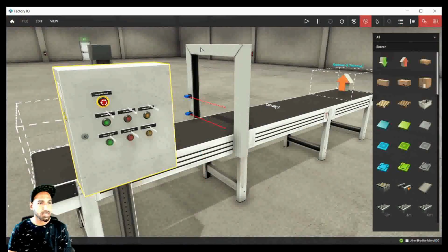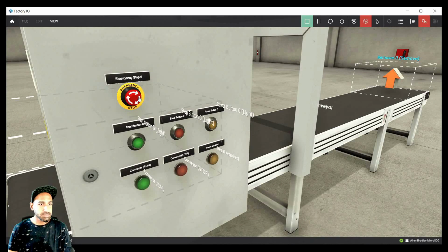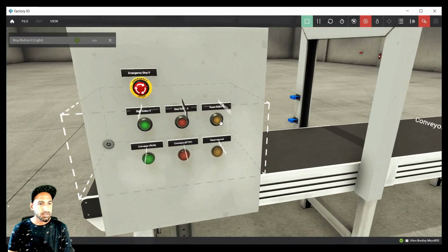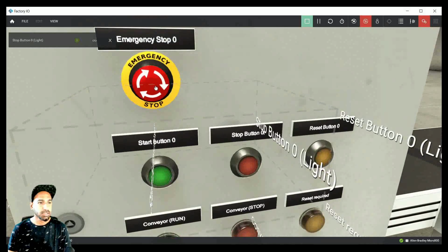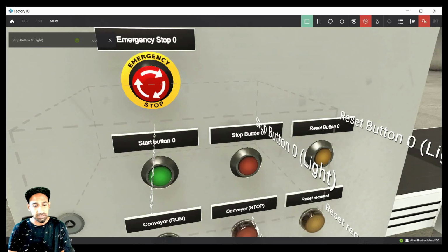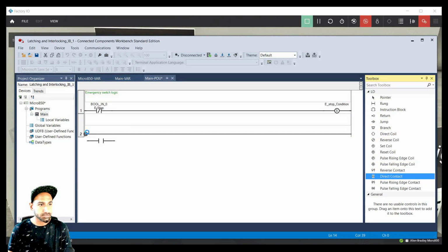switch now, for example, it's very important to know. In our situation, if this is pressed, and if you press reset here, it should not reset the condition unless e-stop is released. This we have to make sure. So if it is in pressed state, this should not do anything. It should only do anything if this is released. This is for the safety. So when this is released, we have an NO contact, which is true for this e-stop.